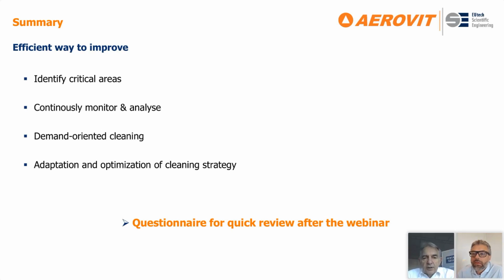There's another question about individual adaptation to automatic identification. There are two sides. We already have instrumentation software where you can define your own critical areas, and image processing routines automatically identify the thickness of soot. For this criteria you can define a limit, connected to a warning and an alarm, so you have different levels, and this information is fed directly to the DCS system or to your cleaning device.